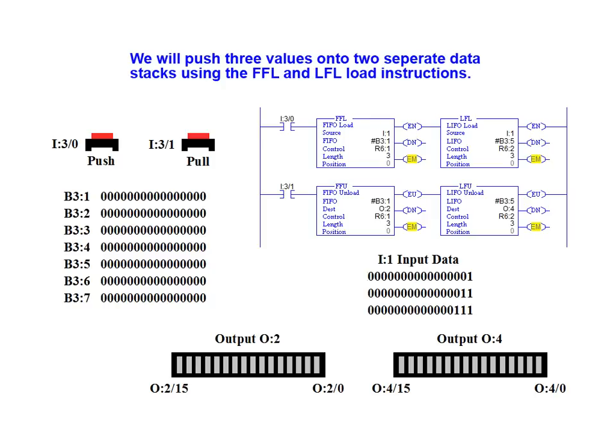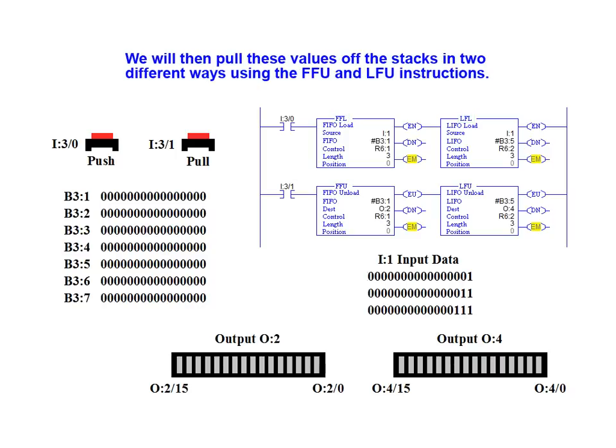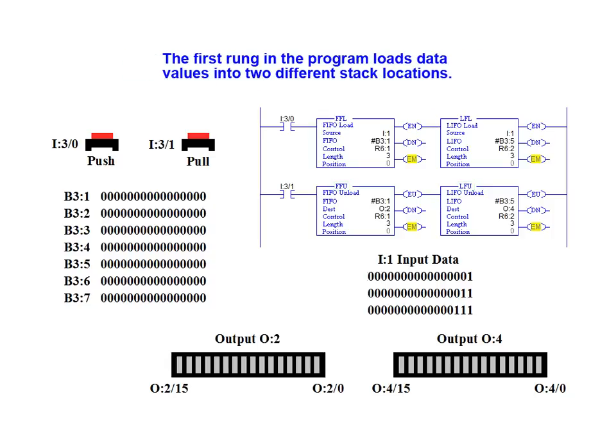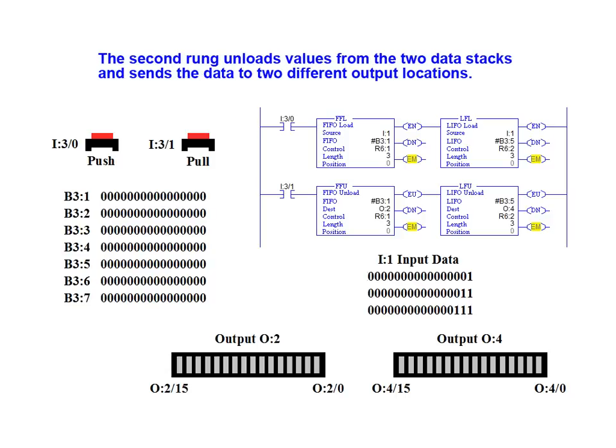We will push three values onto two separate data stacks using the FFL and LFL load instructions. We will then pull these three values off the stacks in two different ways using the FFU and LFU unload instructions. The first rung in the program loads data values into two different stack locations. The second rung unloads values from the two data stacks and sends the data to two different output locations.